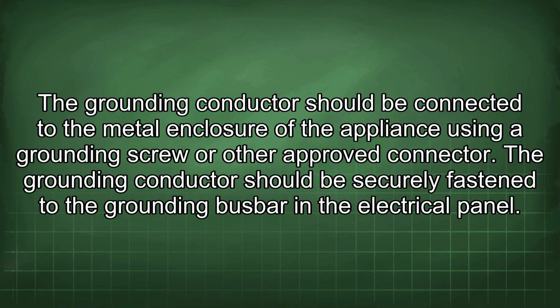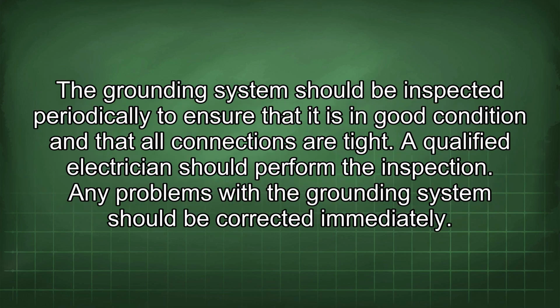The grounding conductor should be connected to the metal enclosure of the appliance using a grounding screw or other approved connector. The grounding conductor should be securely fastened to the grounding busbar in the electrical panel. The grounding system should be inspected periodically to ensure that it is in good condition and that all connections are tight. A qualified electrician should perform the inspection. Any problems with the grounding system should be corrected immediately.